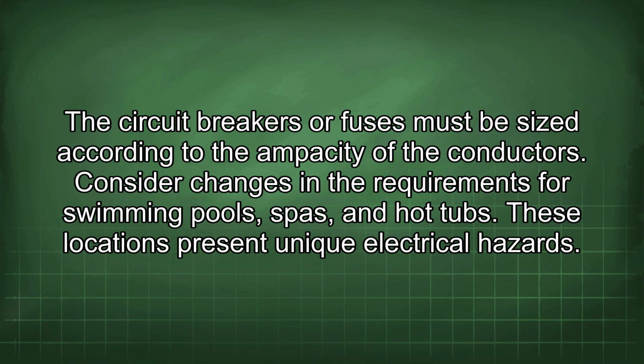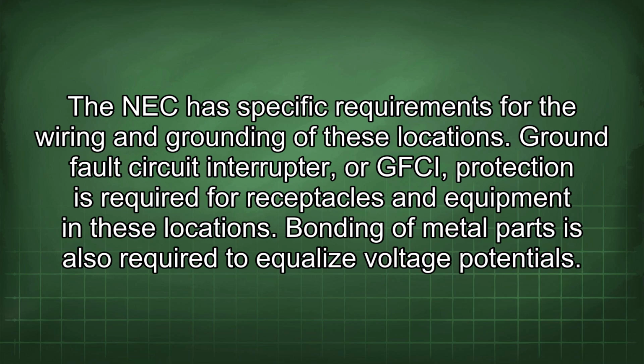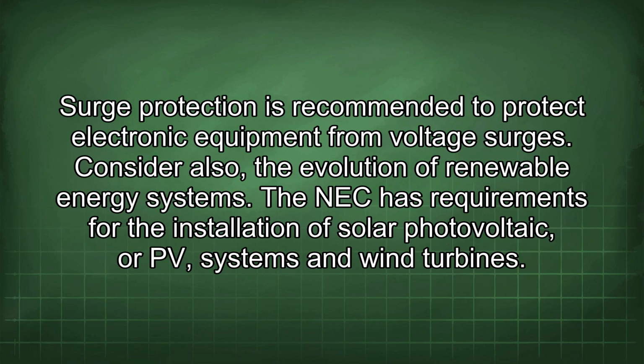Consider changes in the requirements for swimming pools, spas, and hot tubs. These locations present unique electrical hazards. The NEC has specific requirements for the wiring and grounding of these locations. Ground fault circuit interrupter, or GFCI, protection is required for receptacles and equipment in these locations. Bonding of metal parts is also required to equalize voltage potentials. Surge protection is recommended to protect electronic equipment from voltage surges.